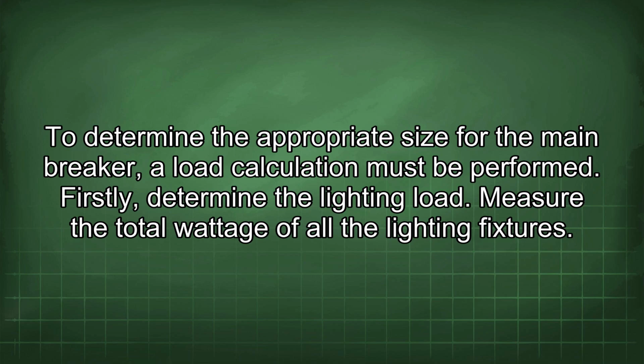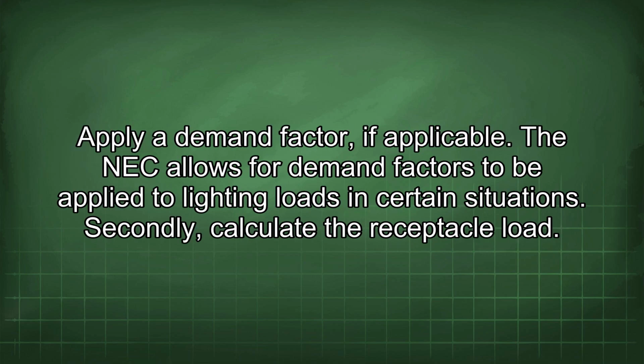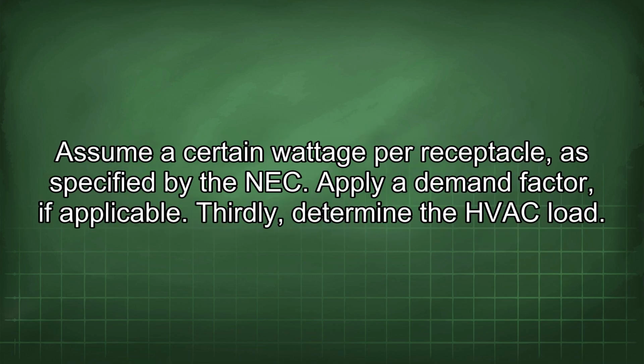Firstly, determine the lighting load. Measure the total wattage of all the lighting fixtures. Apply a demand factor if applicable. The NEC allows for demand factors to be applied to lighting loads in certain situations. Secondly, calculate the receptacle load. Assume a certain wattage per receptacle, as specified by the NEC. Apply a demand factor if applicable.